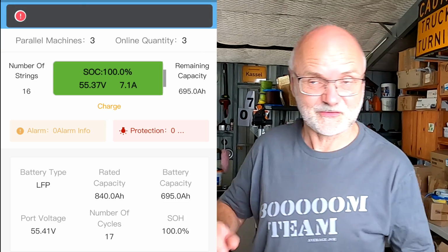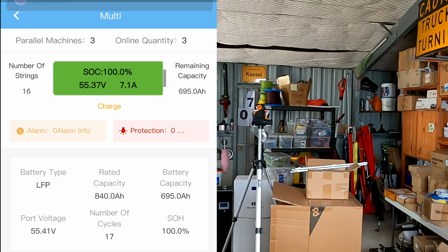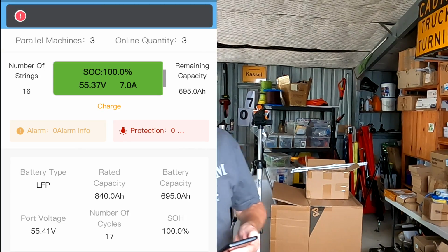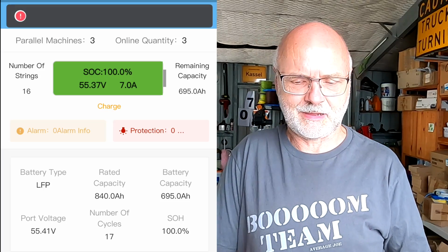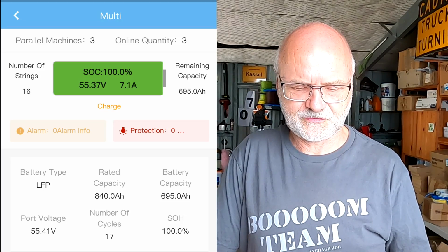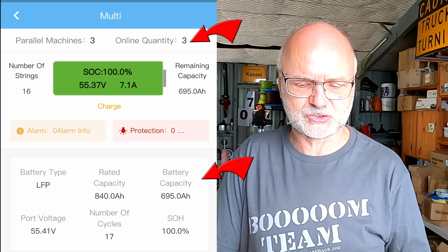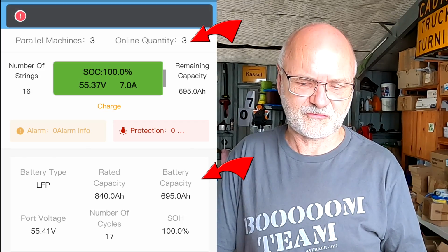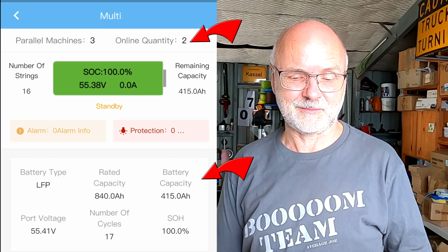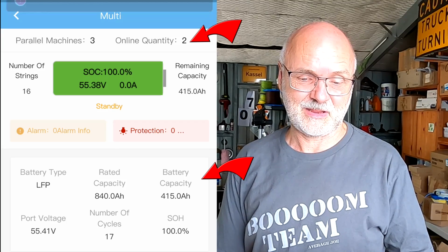If I just go and disconnect the Seplos vertical box - just disconnecting the LAN cable - there's no communication to the master anymore. You should see we still have 3 parallel machines, but only 2 are online. It takes a moment for the master to realize someone's missing, and there we go.